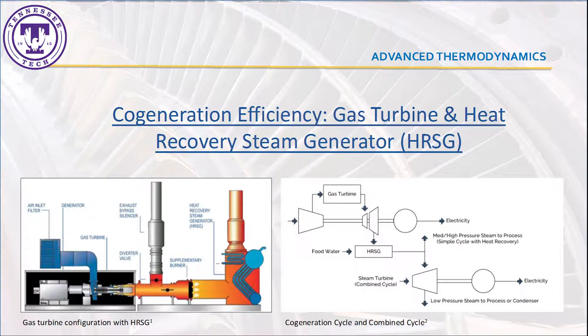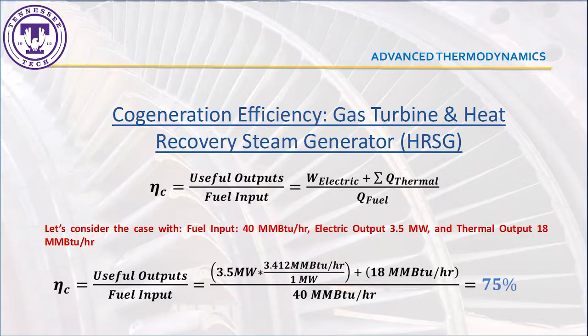Recently, different cogeneration technologies are used to increase the overall efficiency of power systems by the reuse of thermal energy that would otherwise be lost. One of the most common cogeneration systems is based on the substitution of steam turbines with natural gas turbines. This change in technology allows you to improve the efficiency of the system significantly, reducing fuel consumption and saving money, and releasing fewer greenhouse gases into the atmosphere. In a cogeneration system, efficiency is calculated by adding the useful outputs of a system and dividing by the energy in the fuel that is input.